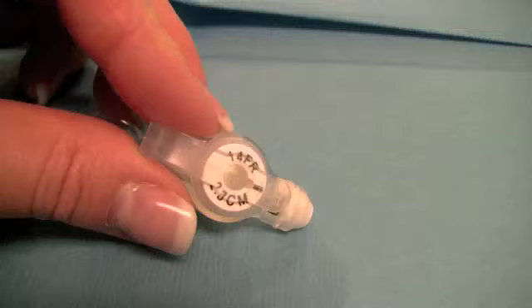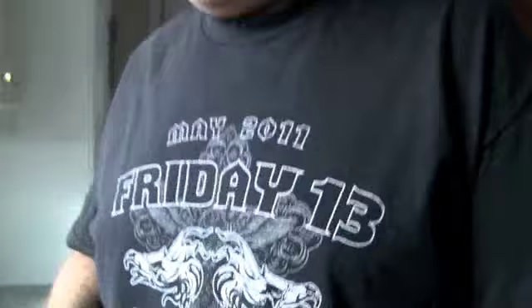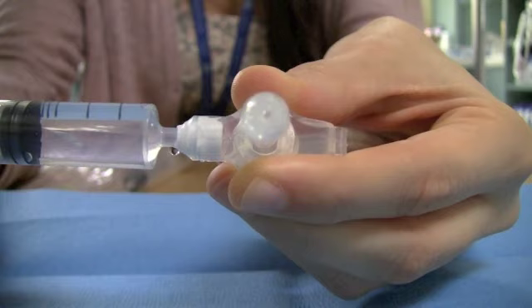While G-tubes aren't new, David was the first patient at Sunnybrook to be fitted with a unique style of G-tube called the MIC-KEY. It sits flush against the abdomen and allows patients much more freedom of movement. Compare the MIC-KEY to traditional G-tubes that protrude several inches from the abdomen and the difference is obvious. The MIC-KEY is much smaller and comes with a detachable adapter that connects when feeding, meaning it doesn't get in the way of daily living. It also differs from traditional G-tubes in that it has a one-way valve that eliminates leakage and spillage, which is a common complaint. It's held in place with a small inflatable bubble filled with water, and users just need to check the water level once a week to make sure it stays positioned properly.